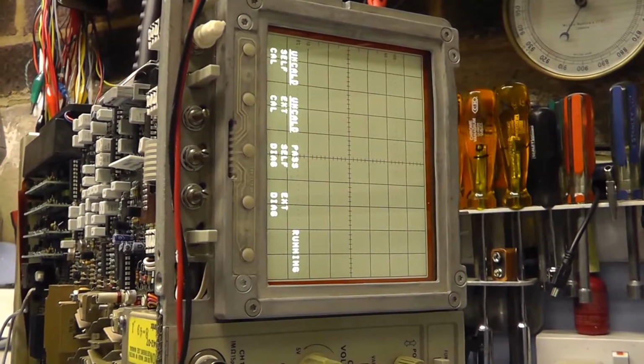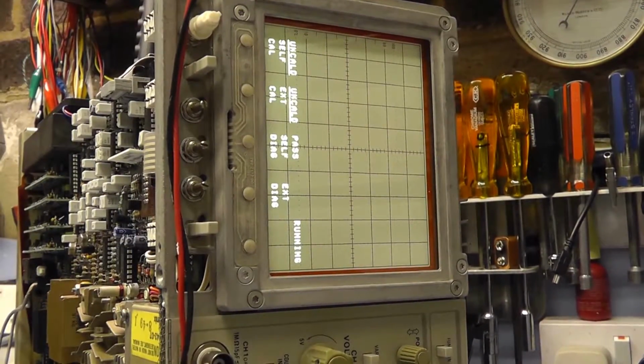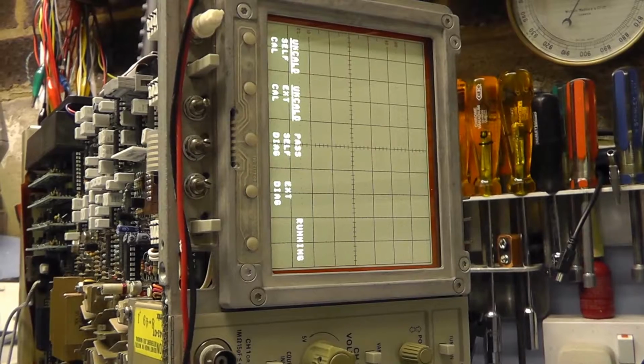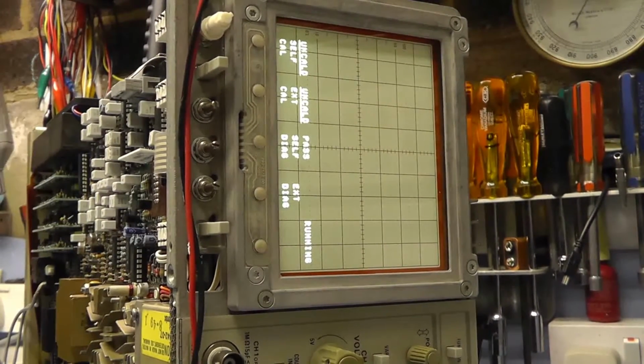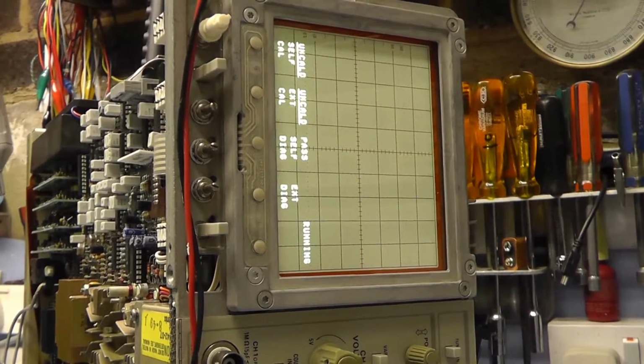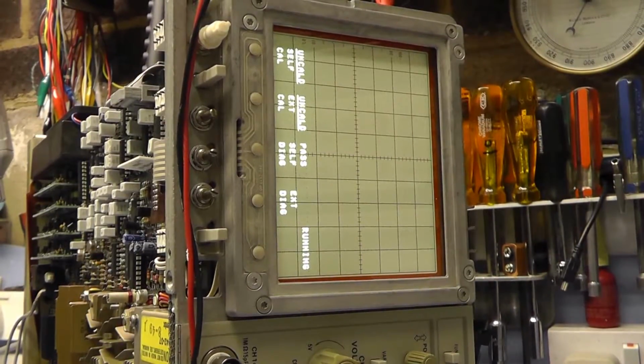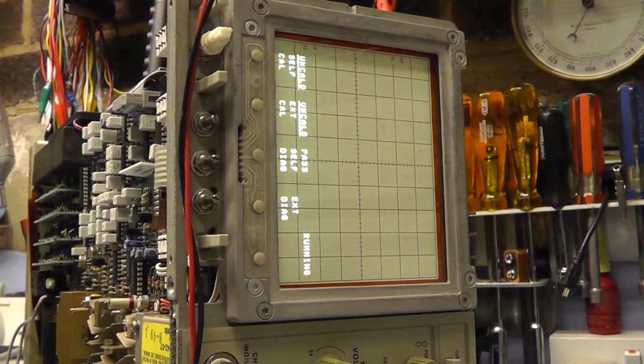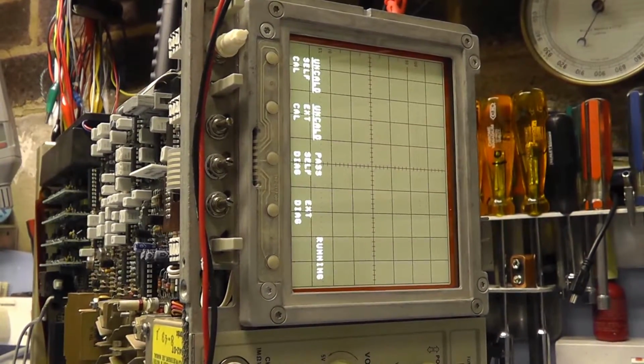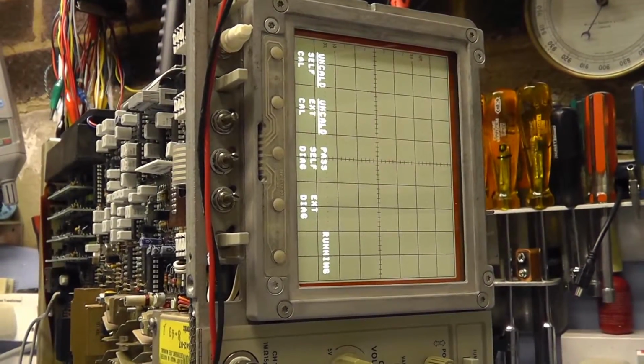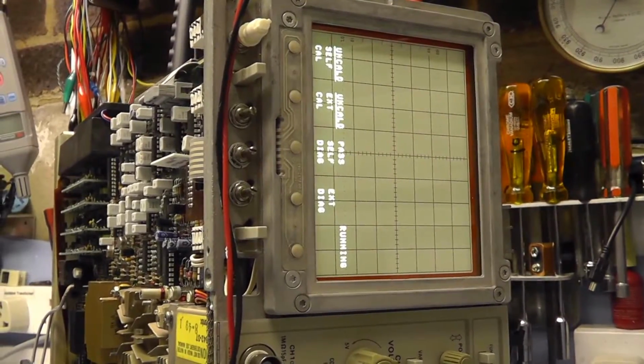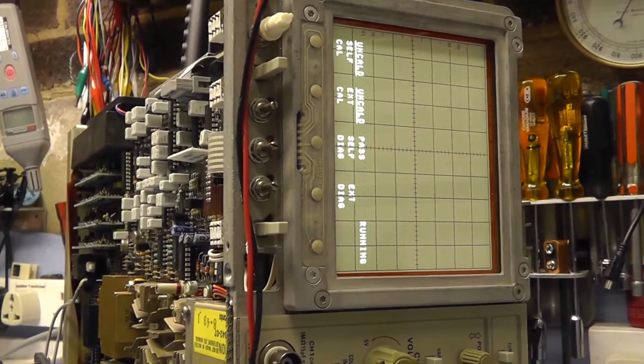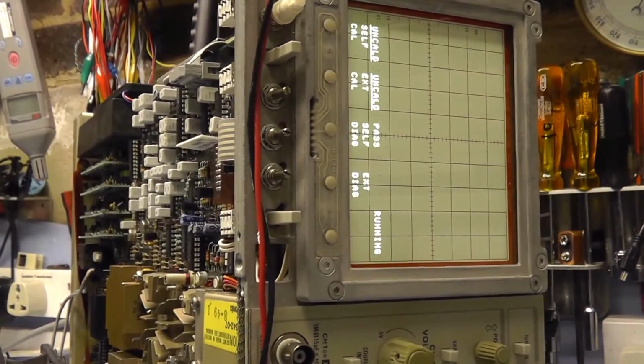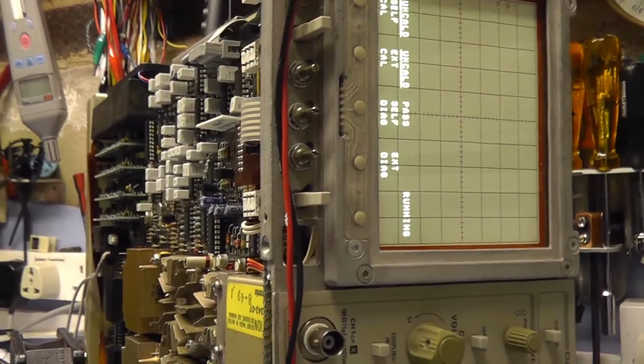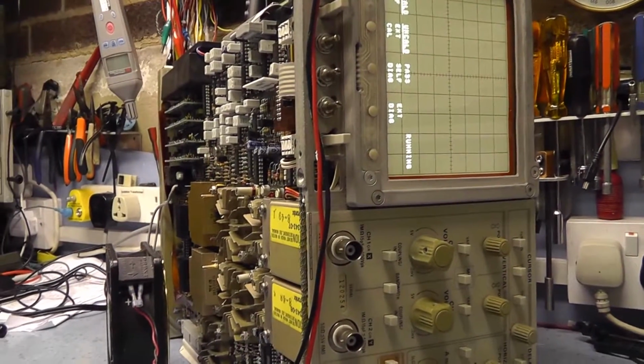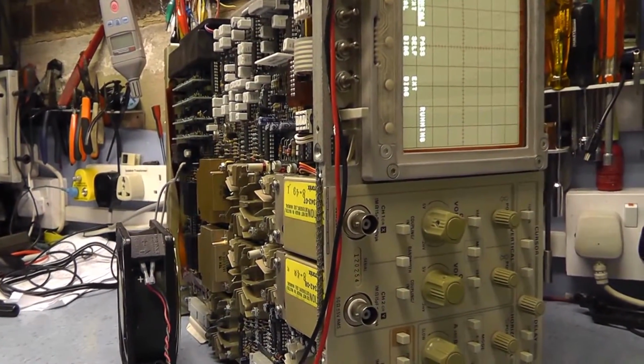But it might be useful - there are a lot of people out there with these scopes who've got the same or similar problem. At least if I can narrow it down to roughly where I think it is, maybe it would give someone a head start. The biggest problem with this scope has been I spent two months looking at a fault listed on the service manual as a voltage that should be 12.2 volts on the DAC output, when that was a load of rubbish. It shouldn't have to be anywhere near that high. So I spent a lot of time chasing a red herring.